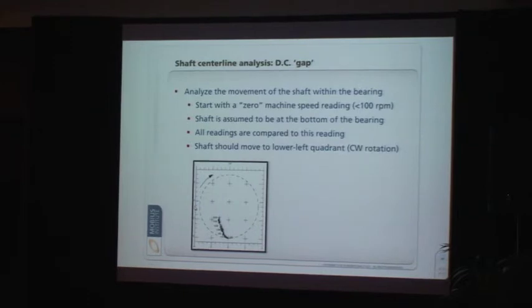What we're doing is figuring out where the centre of the shaft can move. Imagine a circle around the centre of the shaft: if it moved above that point, it would bump against the top, below it would bang against the bottom, left or right side likewise. As the machine started up, the centre was at the bottom of the bearing, just resting there. They may pump oil underneath. As it starts turning and gets faster, it lifts up and moves away from the side of the bearing, with a nice oil wedge sitting underneath it.